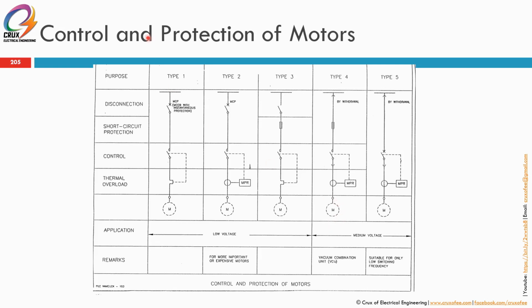So let's see one by one. Type 1 is the most conventional one. We use a bimetal thermal overload, which will be used to stop or trip the contactor. And the short circuit protection is by an MCP or motor control protector, which in this case is an MCCB with instantaneous protection. Type 2 is a little bit more modern. The motor is using a CT feeding to a motor protection relay. It will still trip or open the main contactor, and we are still using the MCP, motor control protector.